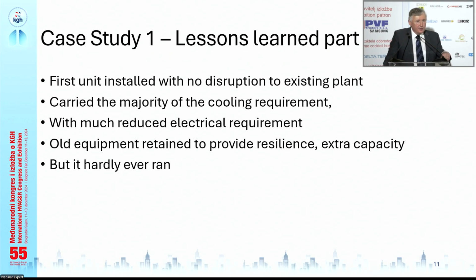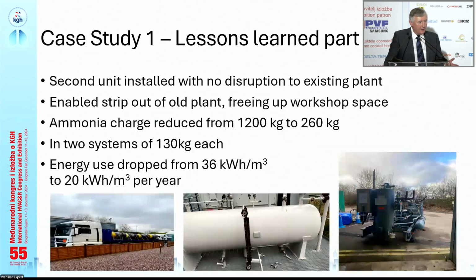So the first unit was installed with no disruption to the plant at all. It was completely independent. We hung evaporators inside the room and we popped the package unit outside. That carried the majority of the cooling requirement and greatly reduced the electrical requirement. The old equipment provided resilience. It was there as backup, but it hardly ever ran. And you can see the second unit also installed with no disruption to the existing plant. It was again a completely independent unit.